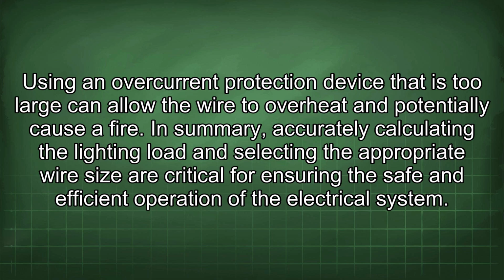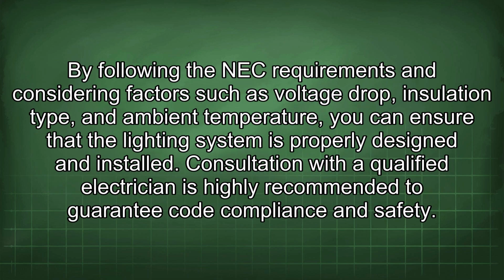In summary, accurately calculating the lighting load and selecting the appropriate wire size are critical for ensuring the safe and efficient operation of the electrical system. By following the NEC requirements and considering factors such as voltage drop, insulation type, and ambient temperature, you can ensure that the lighting system is properly designed and installed. Consultation with a qualified electrician is highly recommended to guarantee code compliance and safety.